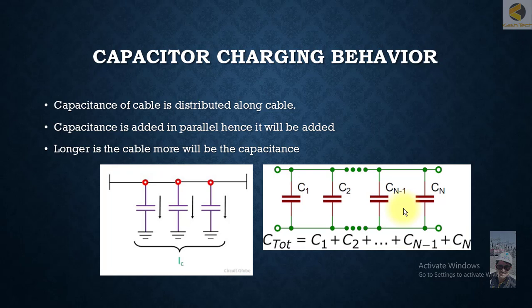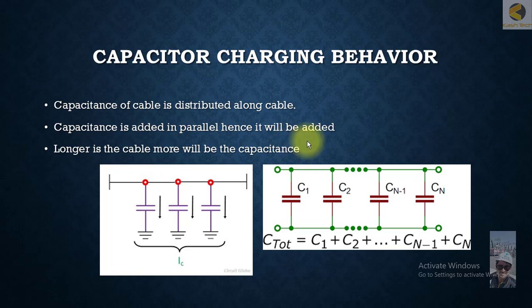Let's discuss the capacitor charging behavior. Basically, insulation cable is also acting as a capacitor, and the capacitance of the cable or equipment is distributed along the cable. Capacitance is added in parallel, so the equivalent circuit for the insulation is a lot of capacitances connected in parallel.